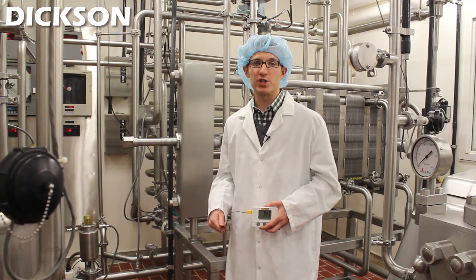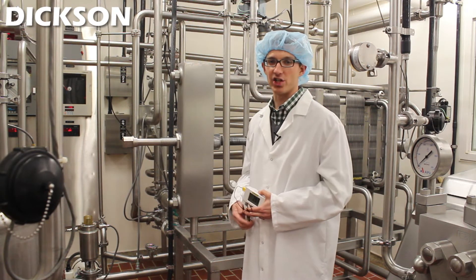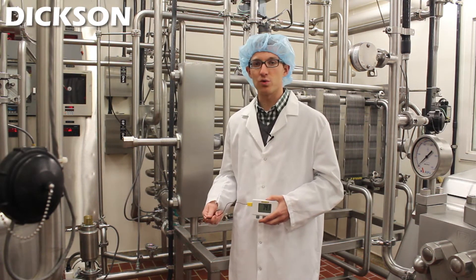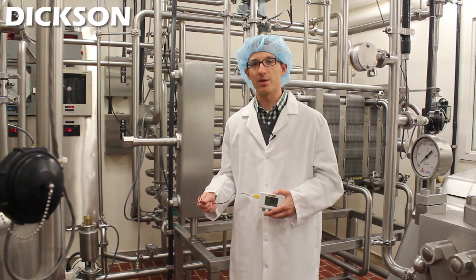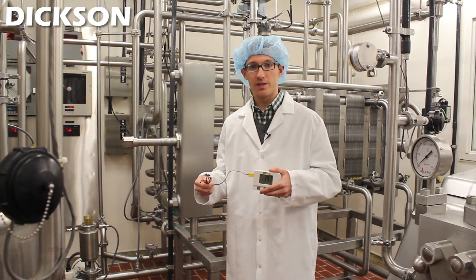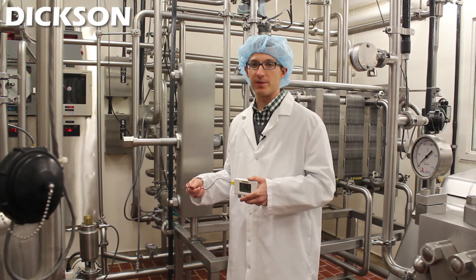Before the raw milk is pasteurized, it's pumped through a series of tubes and into this heat exchanger where it's heated up to 163 degrees for at least 20 seconds. That process can be monitored by using a K thermocouple. Here we have a unit attached to the K thermocouple — the Dickson SM320 — which can record the temperature during that period of time.